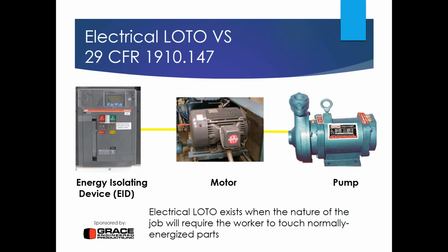In this case, we have an insulated case circuit breaker, an ABB breaker, that in this example is feeding an electrical motor. Through a separate shaft, this motor feeds a mechanical pump. The definition of lockout tagout appears at the bottom of the slide. It says that electrical lockout tagout exists when the nature of the job will require the worker to touch normally energized parts. So we're not talking about systems that become inadvertently energized. If it's designed to be energized and you're going to touch that with any part of your body, you are going to need to use electrical lockout.